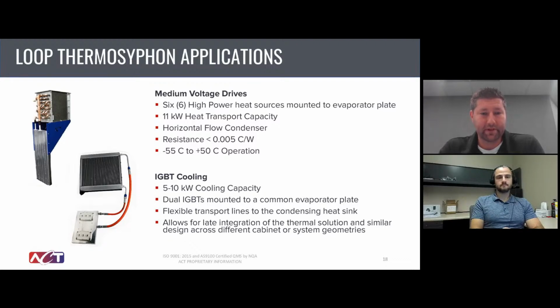So this was the example I was alluding to, with multiple high powered sources on that single evaporator plate. The metallic, silver aluminum plate that you see there coming vertically had 6 heat sources mounted to it. So 3 on one side, 3 on the opposite side. It used refrigerant as the working fluid, and again, transferred that heat in the schematic you saw on the previous slide to an air-cooled condenser. And this one had a fan coupled with it and utilized that heat sink that you can see there with some horizontal airflow.